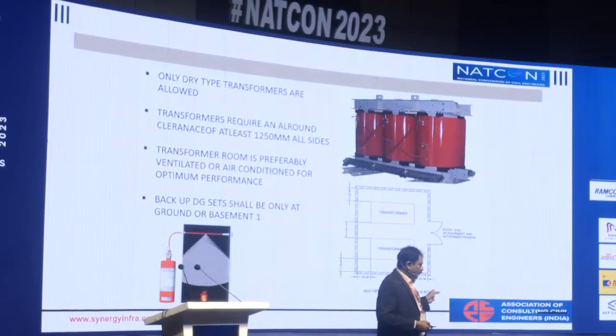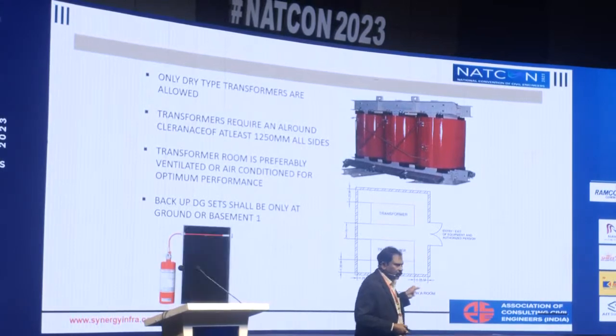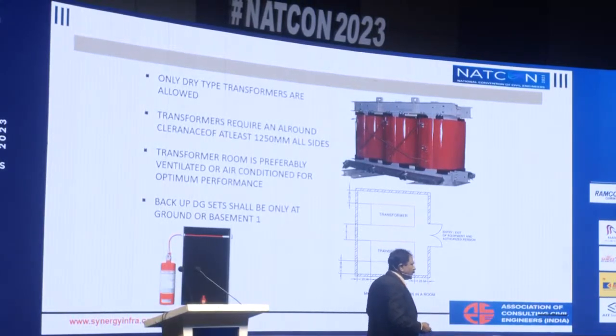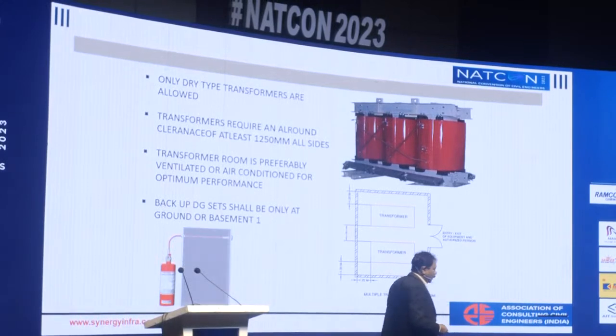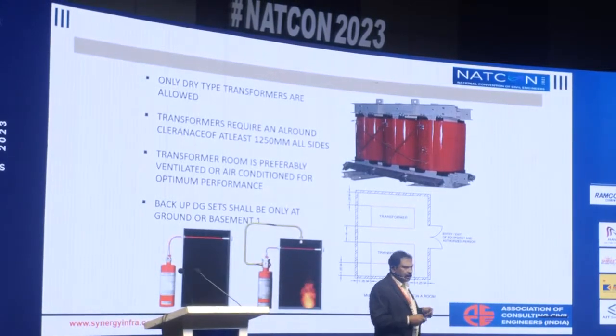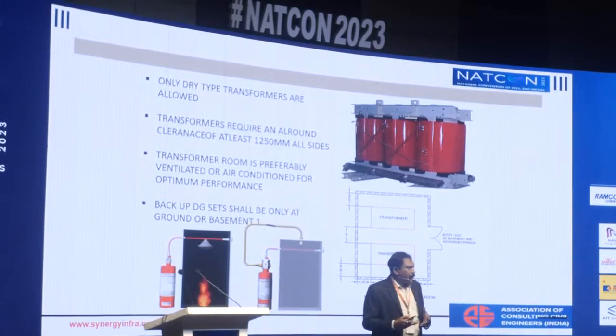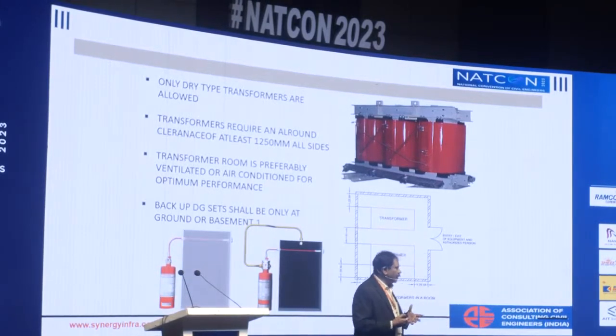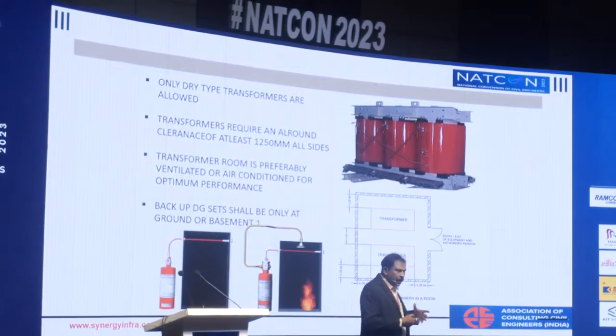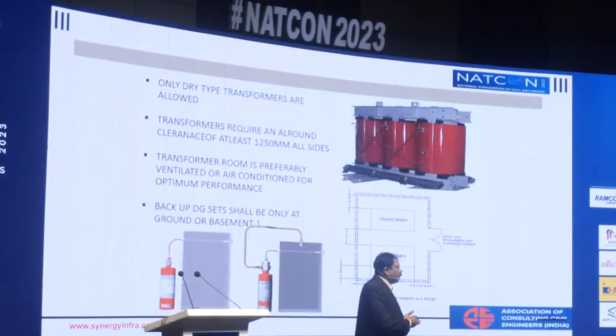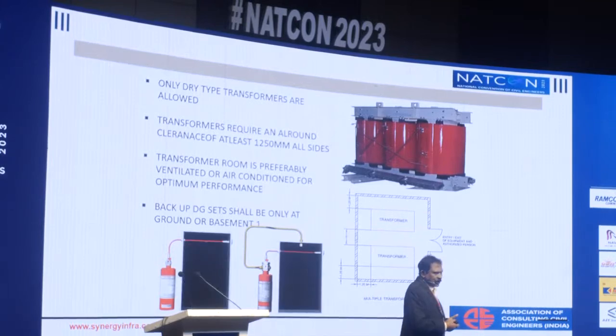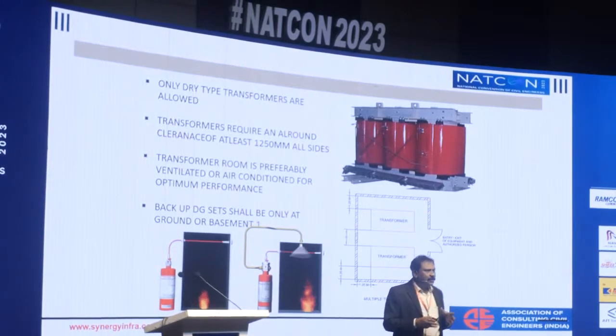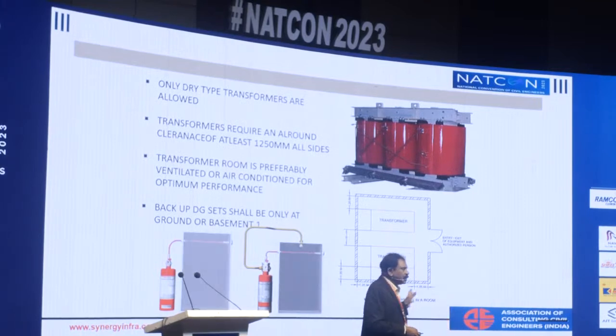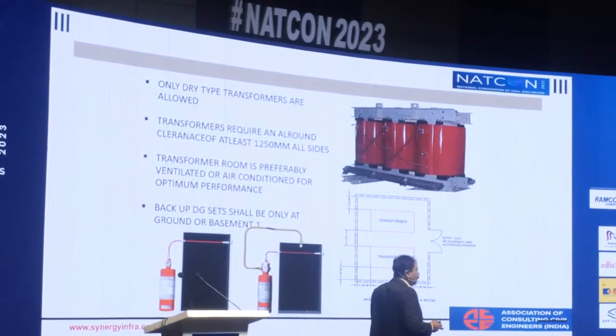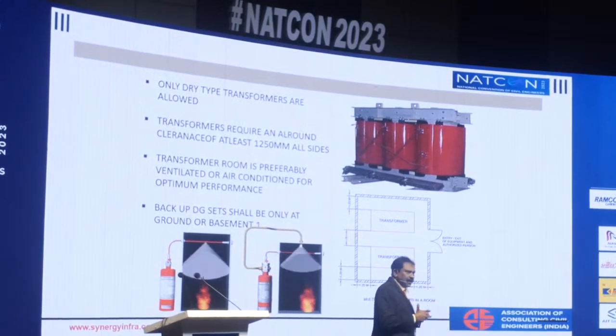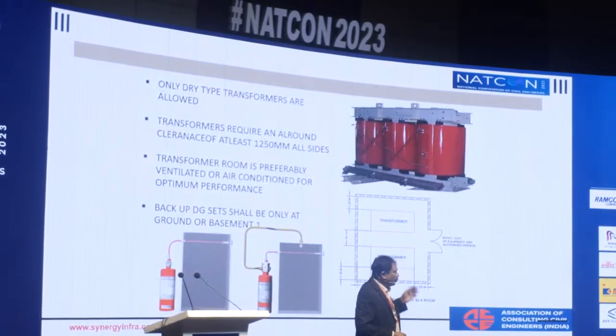And also, for most of the electrical panels, this is one of the requirements by the National Building Code, where we need to have a CO2 or halogen-free inert gas extinguishing system, which is connected to the panel. Whenever there is a fire or some kind of sparking or a temperature rise within the electrical panel, in the main panel or in the lifts panel or in the emergency supply panel, we need to have these kinds of systems built into the panel itself. This is in addition to the fire suppression systems like sprinklers and detection systems and other things.